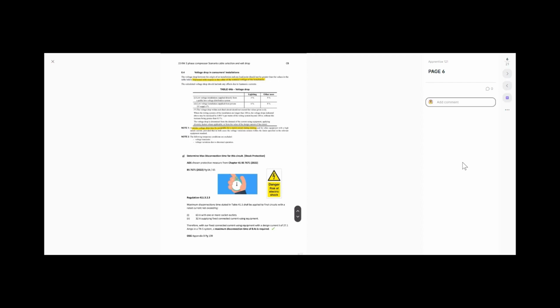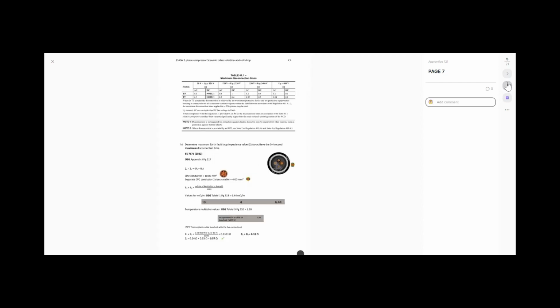411.3.2.3. This gives us information to determine the maximum disconnection time based upon the load and based upon the earthing arrangement. So maximum disconnection times that are stated in table 41.1, I've included the table in here, shall be applied to final circuits with a rated current not exceeding 63 amps with one or more sockets. This circuit isn't a socket outlet, or up to 32 amps applying to fixed connected current using equipment. Well, this circuit is 27 amps and it is a piece of fixed current using equipment. So what we need to do now is look in table 41.1, and we need to have a look at the earthing arrangement to find out what our maximum disconnection time is for this circuit.